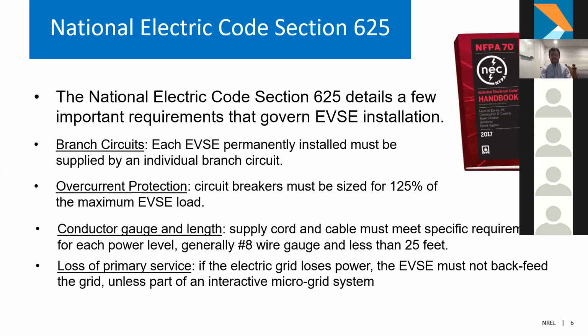So there's a few key elements in the National Electric Code that I want to touch on, but this section 625 that details all of these installation requirements specific to EVSE is rather vast, and there's a lot of very specific requirements and small little caveats here and there that are very important to consider if you're doing a larger installation or you want to make sure that you're abiding by all of the guidelines here. But the most important thing that I think everyone should be aware of is if you're installing, say, a permanent EVSE unit, each one of those should be installed on what's referred to as a branch circuit.